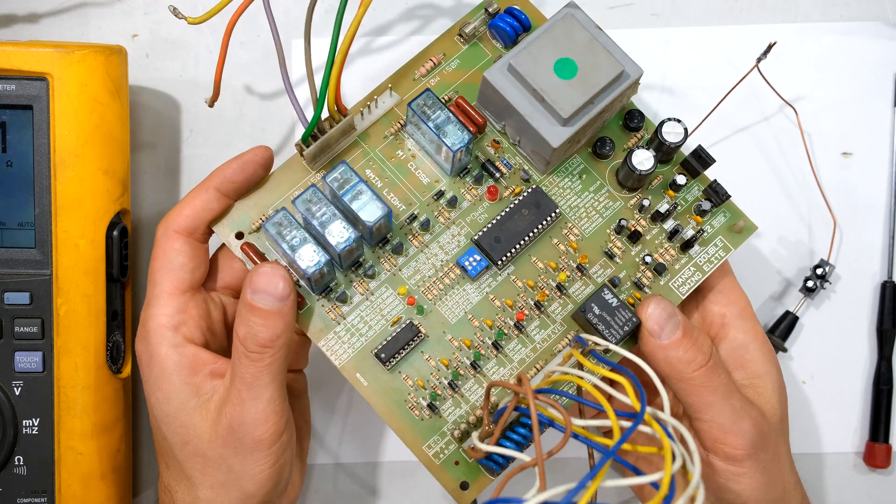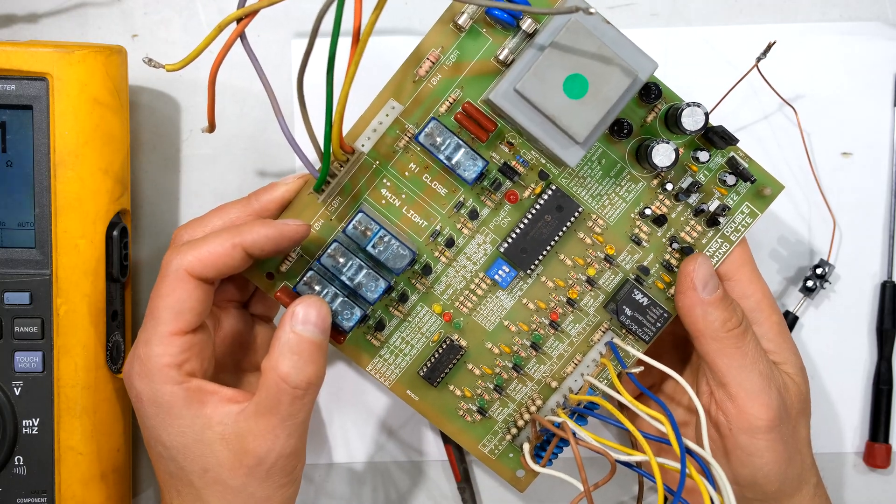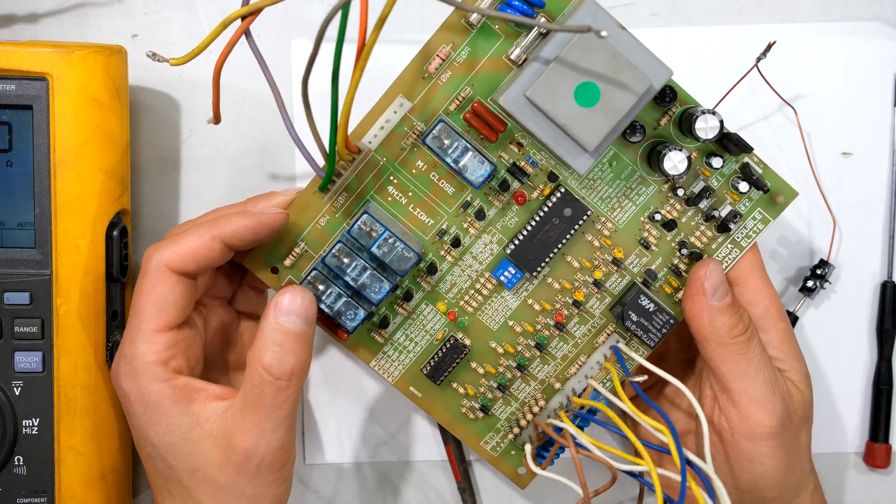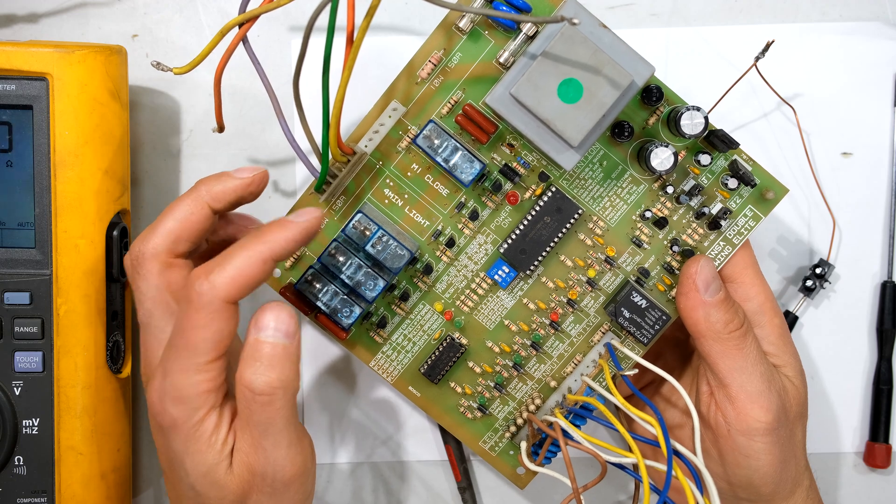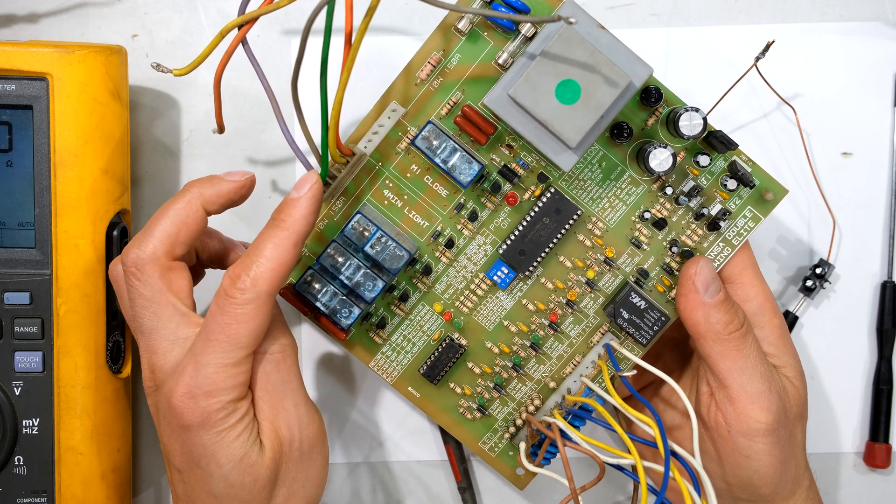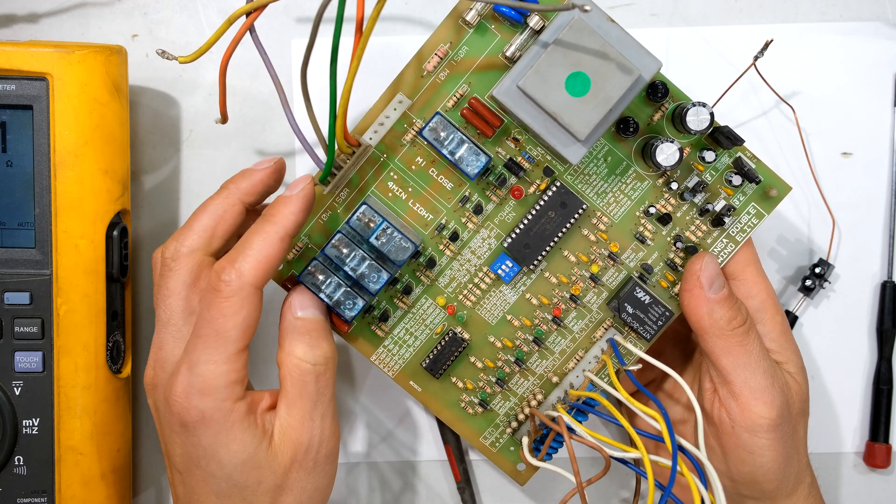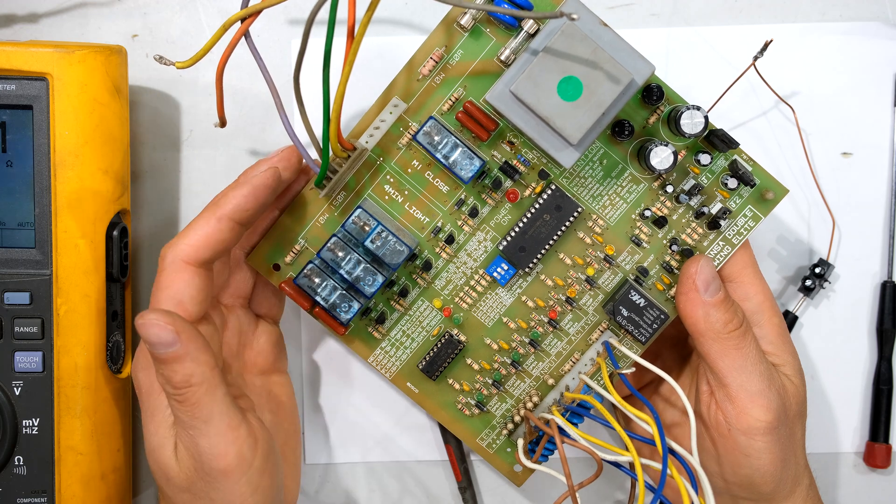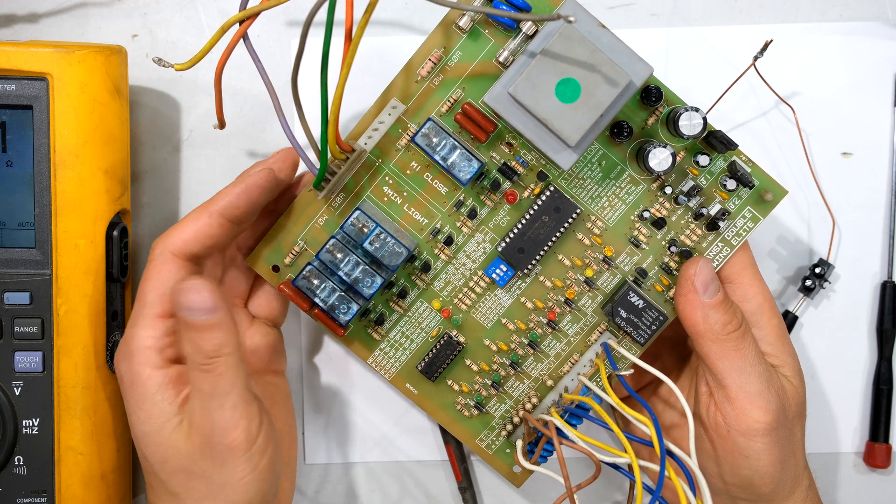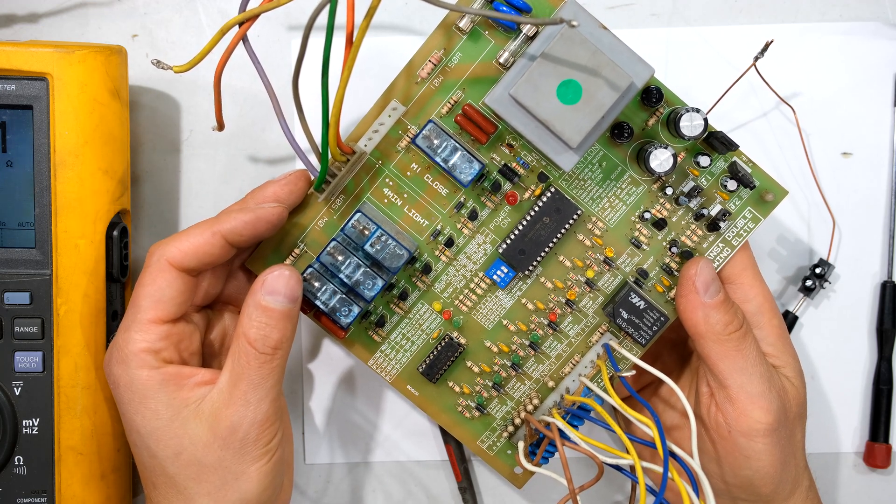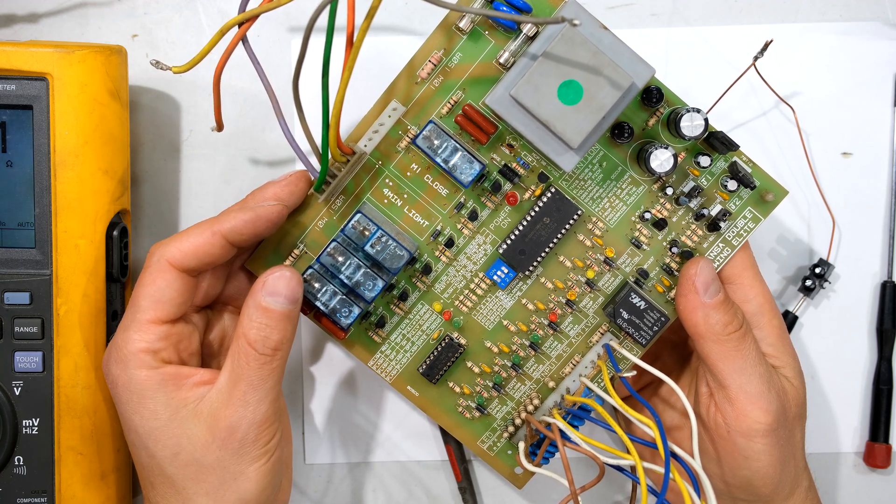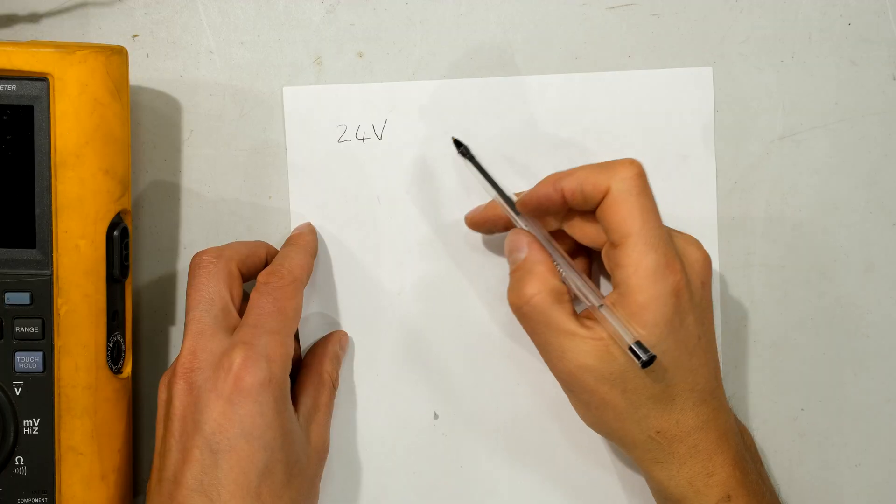For example, this is a 24 volt system and there's quite a few contacts that are made in this one circuit. There are two at the relay, one here, one on this side, then at the motor side there are two. So if we add up all those contact resistances and then we do a calculation, which I'll show now: this is a 24 volt system and the current is 12 amps.